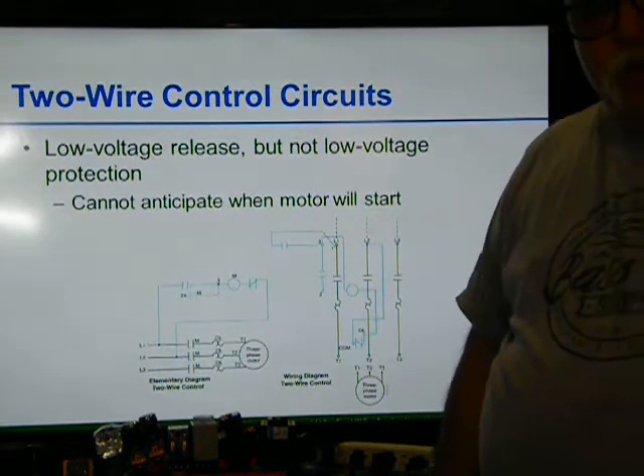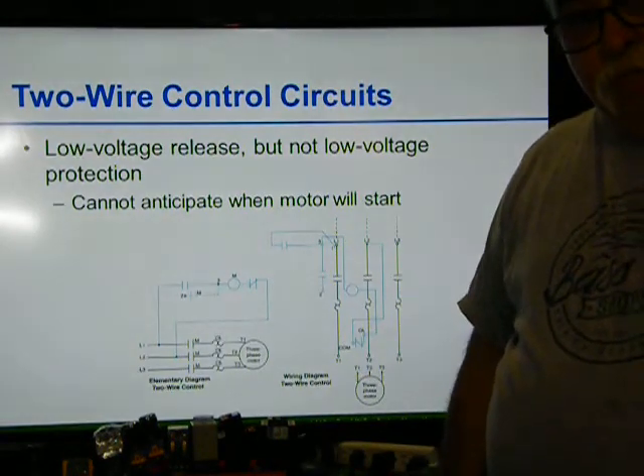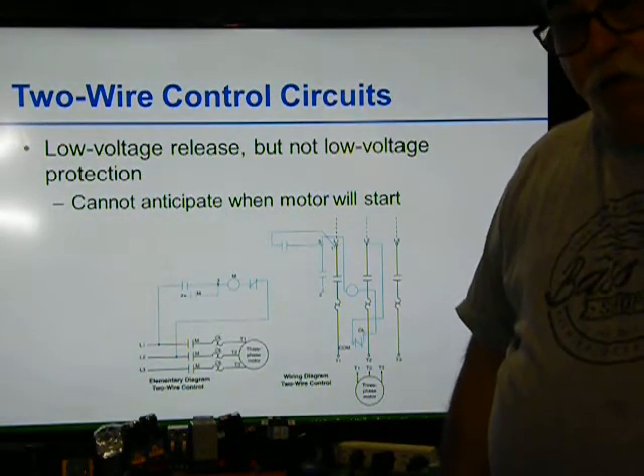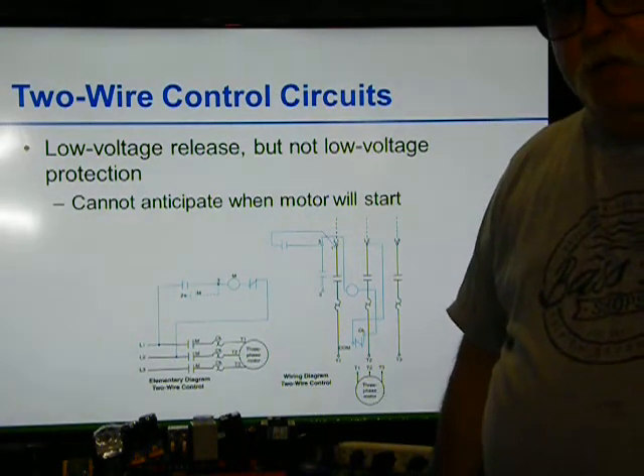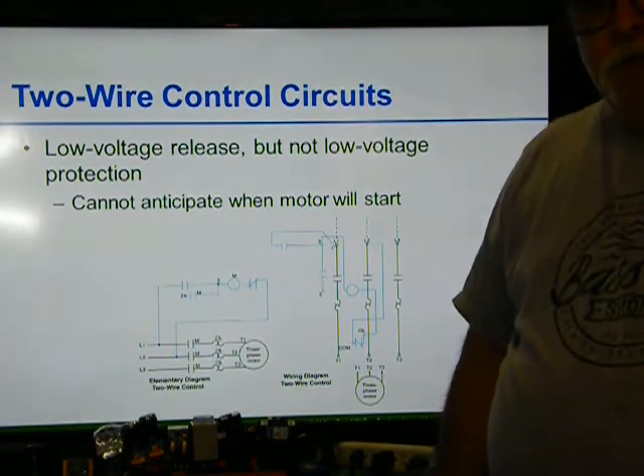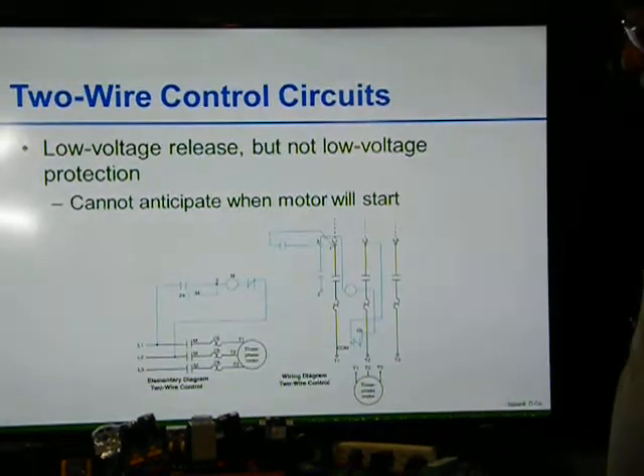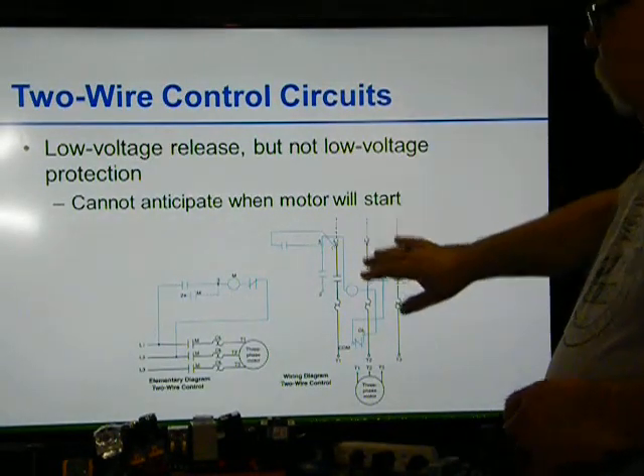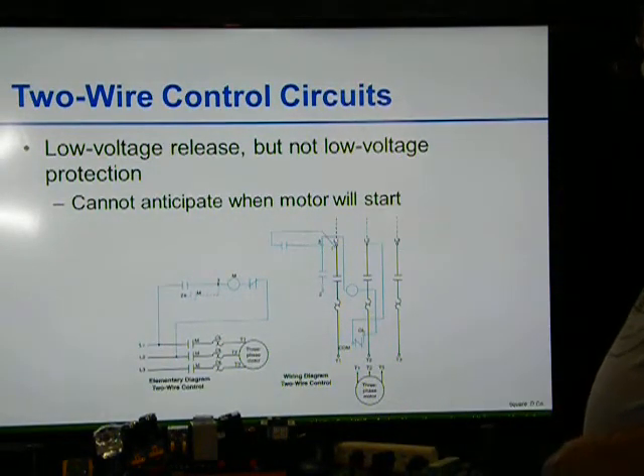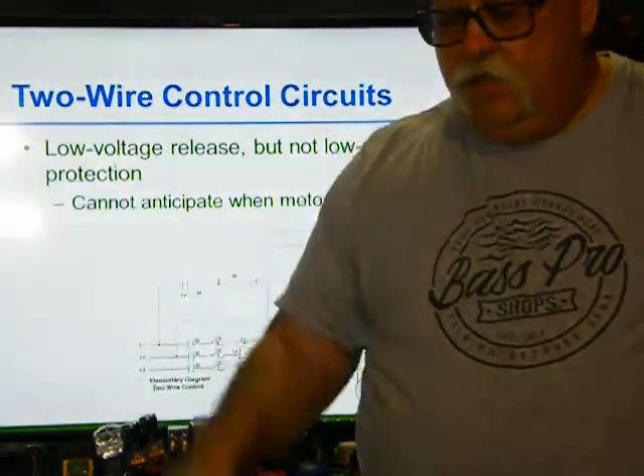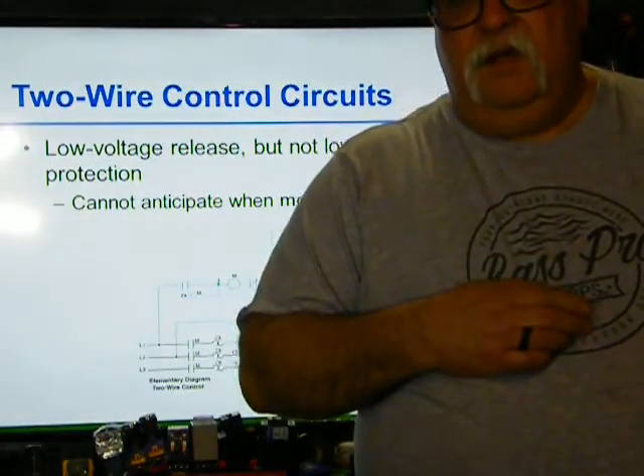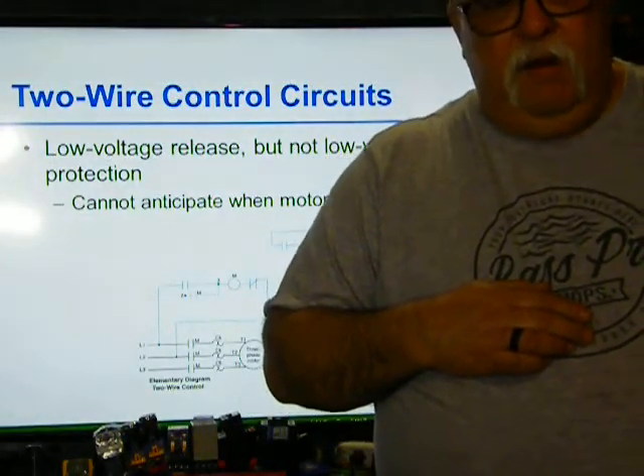But it had a switch. So if power went off, the exhaust fan went off, but when power came back on, that exhaust fan came back on. Why? Because it had to run 24/7, because you never knew when somebody was going to be in there working. And you cannot anticipate when the motor will start. Unless you're standing at the switch, if power's on and you see the switch in the on position, guess what? It's working. If you walk away and leave it in the on position, and power goes off, guess what? You don't want it to come back on.